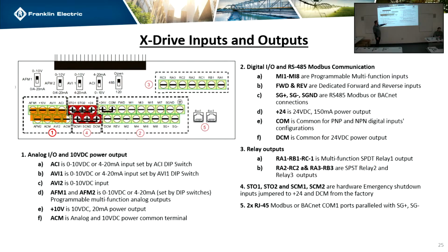Yeah. You can change what they're programmed to, so you can do basic stuff like what's the speed of the motor, or you can do things like replicate your input. So if you want to make sure that the drive is actually seeing your input and you're giving it a 0 to 10, you can have one of these replicate the 0 to 10 so that your system sees it coming back from the drive.